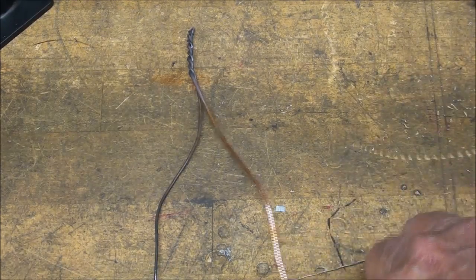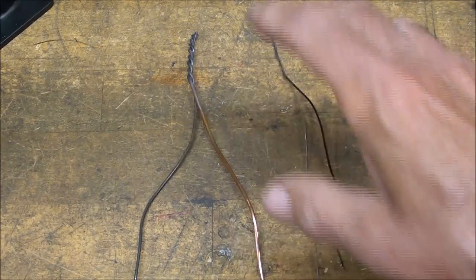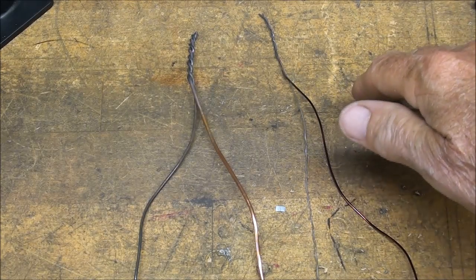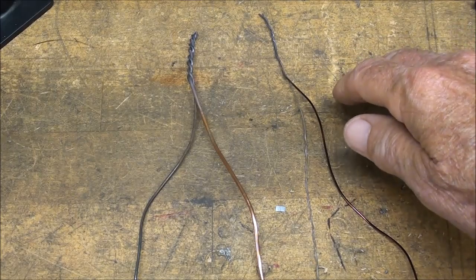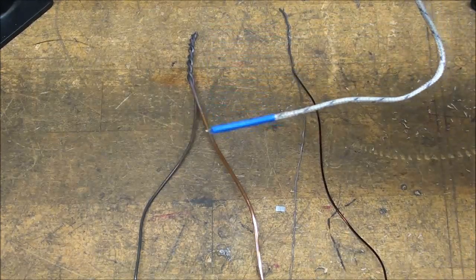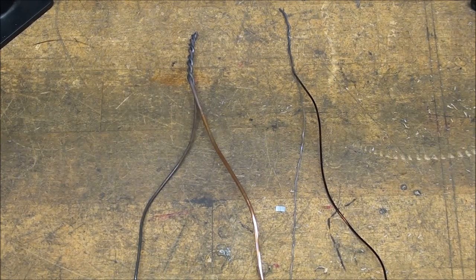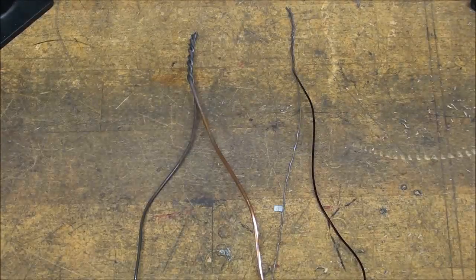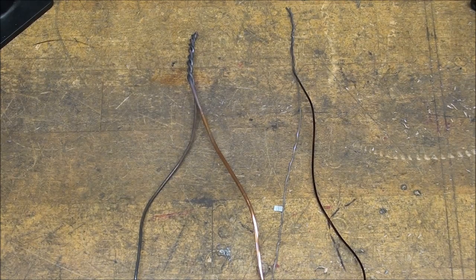Now I've got a couple others that I made too, and here's one that is copper and aluminum. So really, virtually any two dissimilar metals will work, but some are so much better than others. Probably the very best that is known by man is platinum and different alloys of platinum, but that is so terribly expensive that it isn't used except in laboratories. But in common pyrometers, very commonly they use chromel and alumel. Chromel is a chrome and nickel alloy, and then alumel is aluminum and nickel. There's a lot of other different ones that they might use, but those are ones that are tried and proven in laboratories and have been used for years and years with great success.